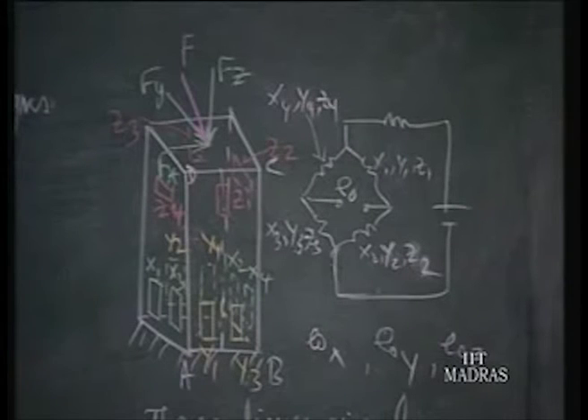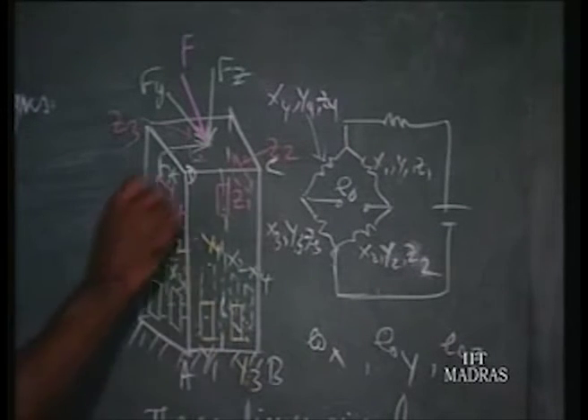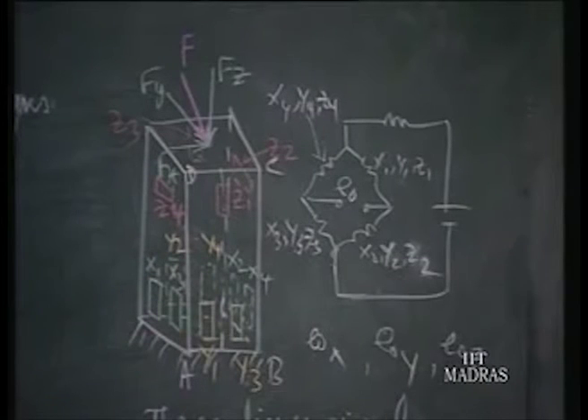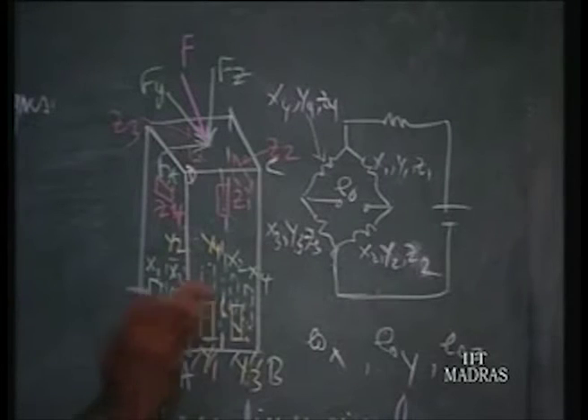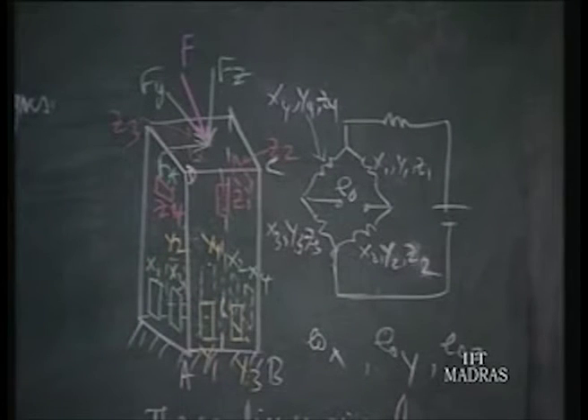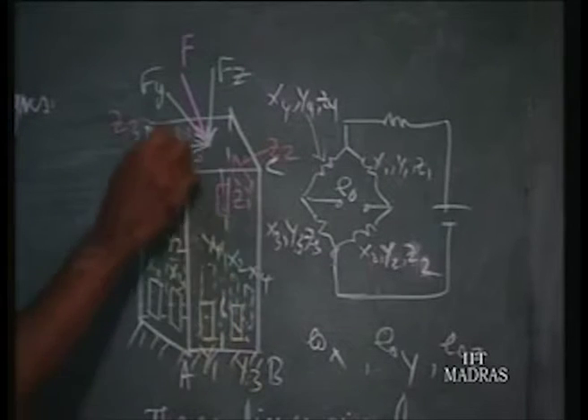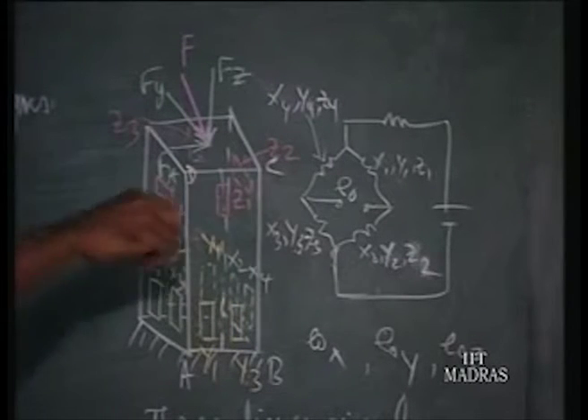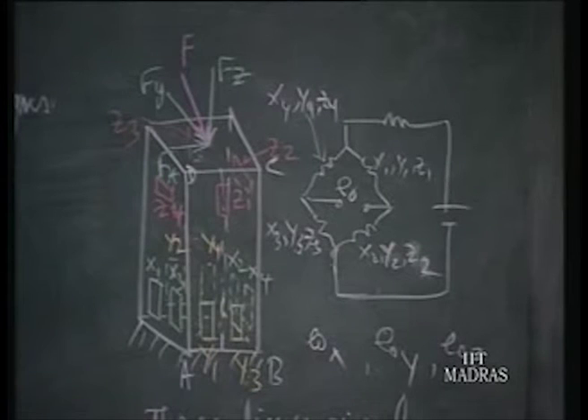Within the strain gauge itself, it gets cancelled out. So instrumentation for one direction force will not be influenced by the other direction, provided the strain gauges are fixed symmetric about the neutral axis on each face. So for Fx and Fy, we have got 4 strain gauges. Similarly, Fz is column type, so you cannot have all the 4 axial directions.